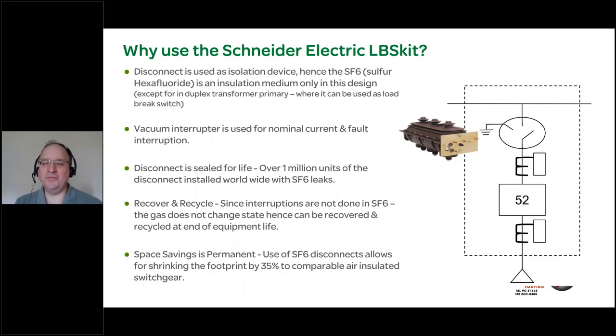The switch itself that we have grown to love over time is the Schneider Electric LBS kit, load break switch kit. Some people call this the Schneider Electric HVLCC because the same switch is used in Schneider Electric fusible switchgear designated HVLCC. You can see, if you look here at the switch, these two brown, they look gray here, circles, those are the viewing ports from the front of the switchgear, where you can look inside the gear, and it does require a flashlight to do so, and meet the NFPA 70E Article 120.5 requirement for visible confirmation of blade disconnect, as well as visible confirmation of grounding.